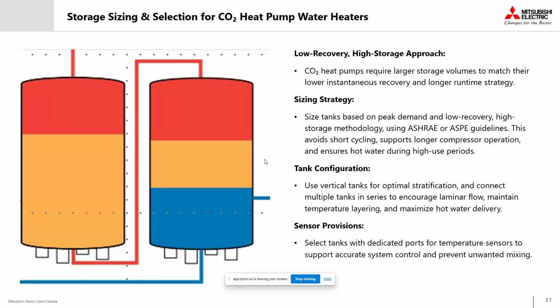Another aspect that we want to consider is that for a lot of these low recovery, high storage systems, we're looking to use vertically configured tanks. In the example we see here, we've got multiple tanks connected in series, and we're looking to promote laminar flow and stratification within these tanks. Another thing we need to consider is to plan for dedicated ports for our temperature sensors to ensure precise system control and water quality.